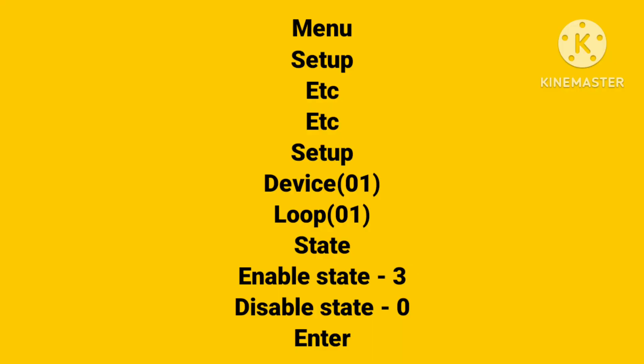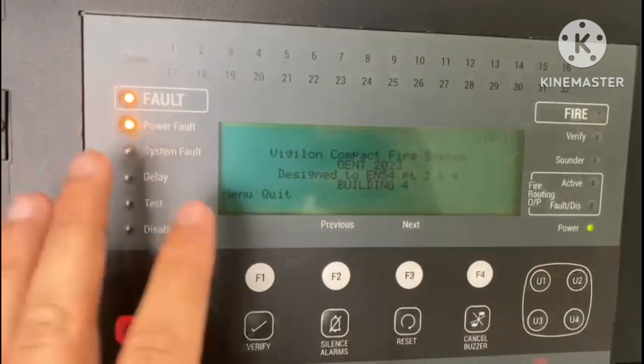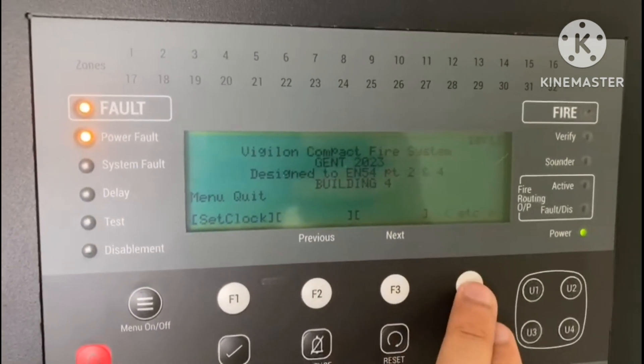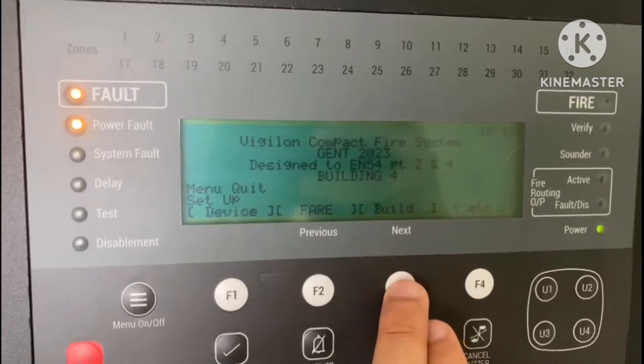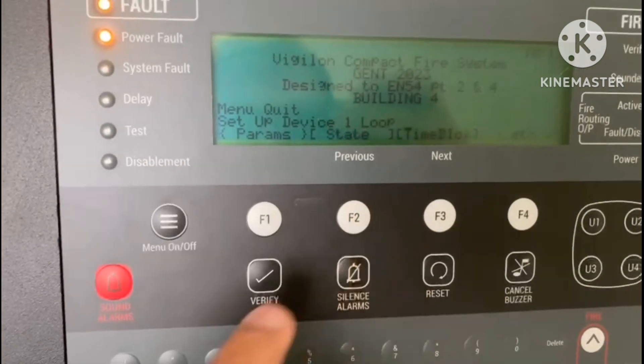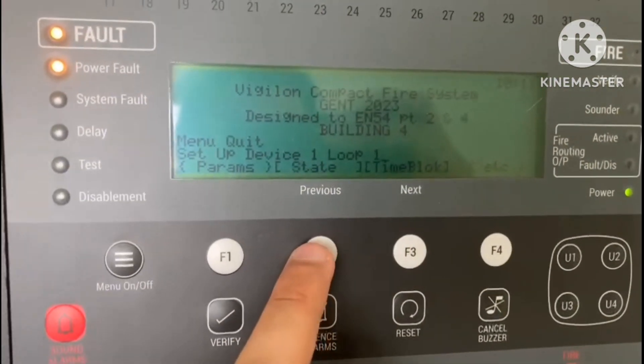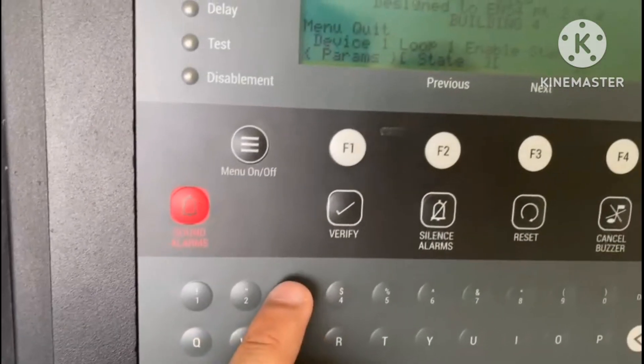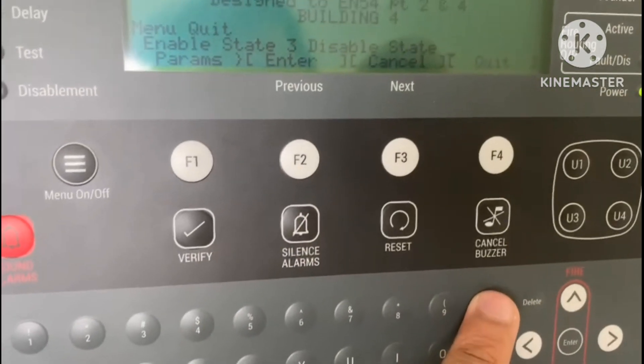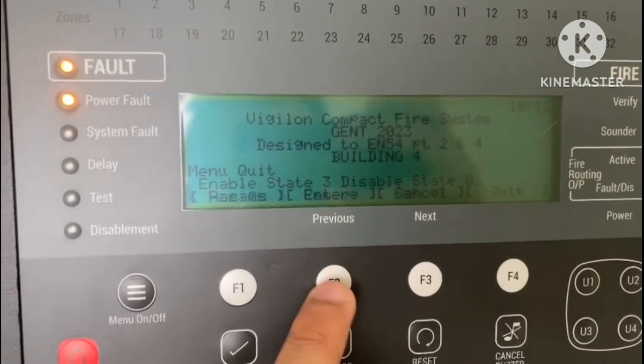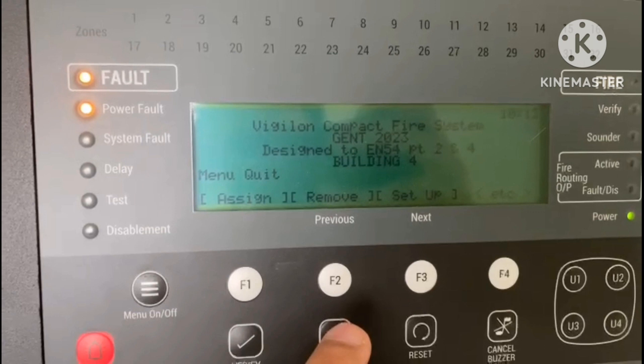To set the state on the panel, go to: Menu > Setup > etc. > Setup Device. Enter the device number, then the loop number, then enable state — whatever state you need — then disable state (you can put zero or anything). For example: device number 01, loop number 01, then your desired state such as state 3. Then press Enter. You can also check in the device status to confirm whatever you have set.